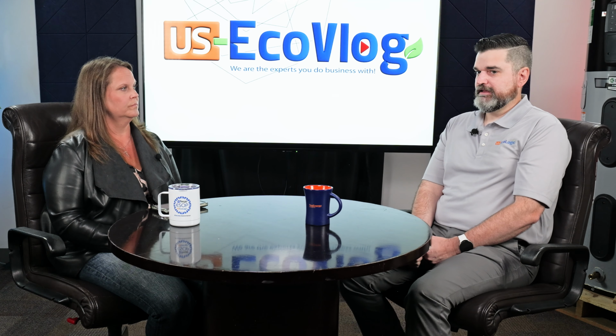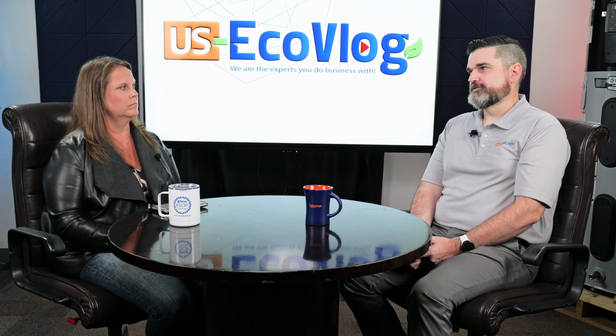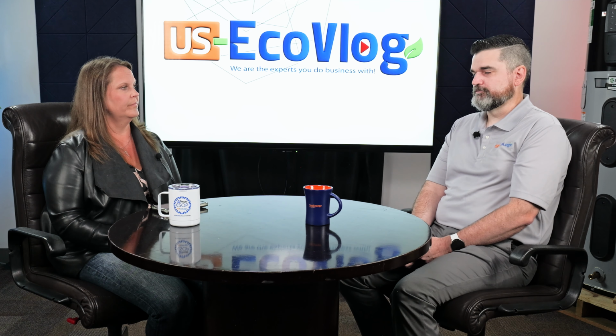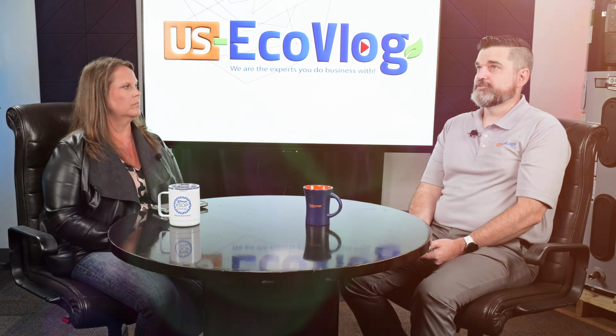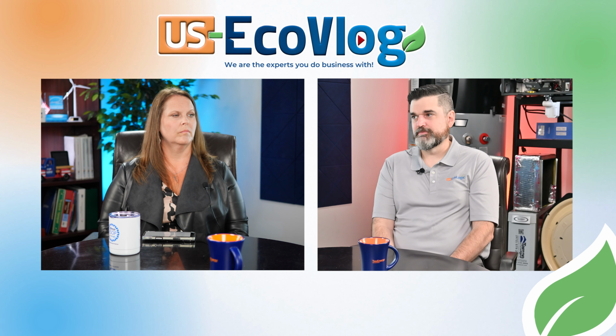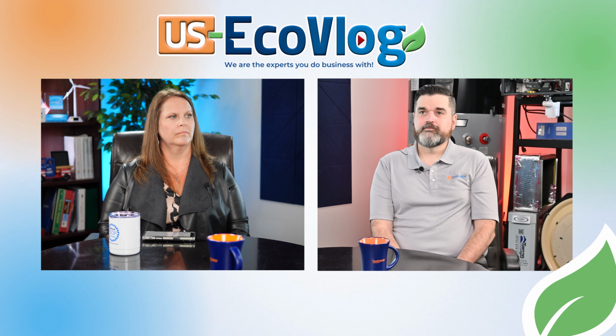The bigger sizing thing, I've worked in this for 20 years now, and there's always somebody who says a half ton bigger than the load calls for is better. If you do that, you're going to start short cycling the air conditioning system. Some aspects mean there's less electricity being used, but the key is it's not pulling humidity out of the air enough.